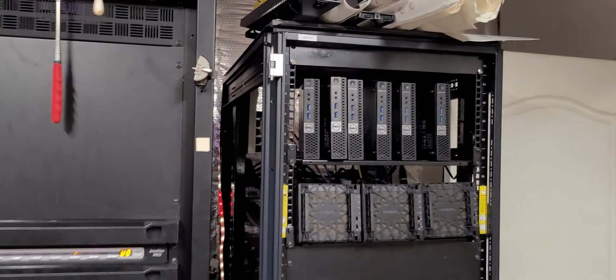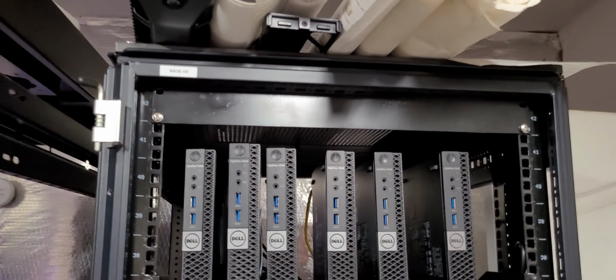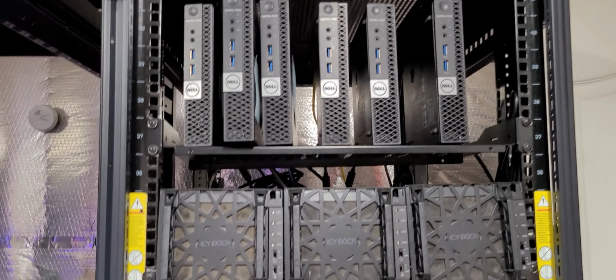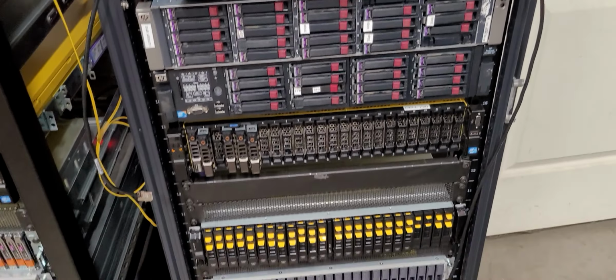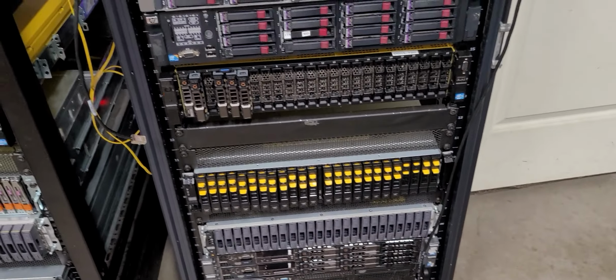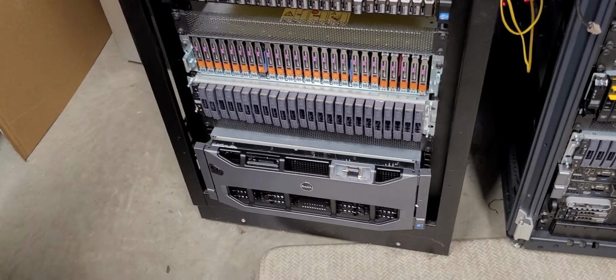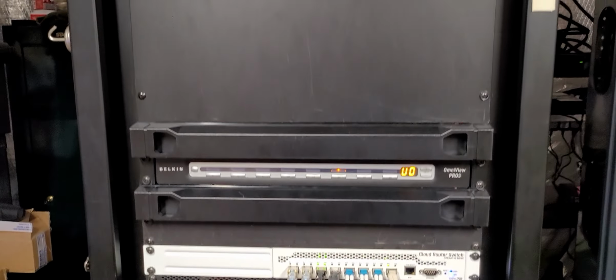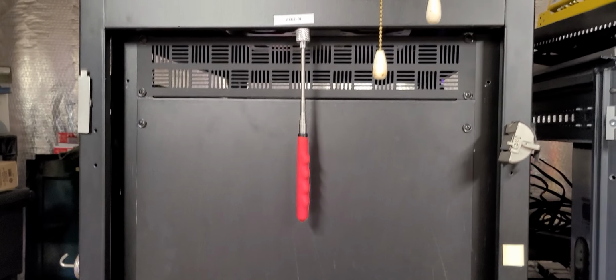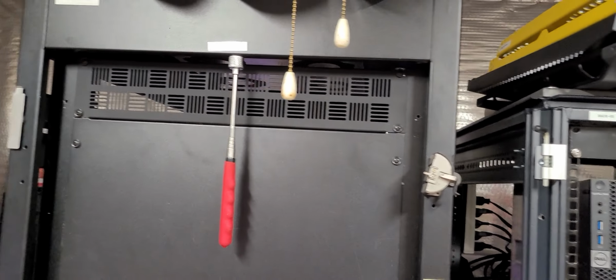Now, obviously, the square footage, that's height, width and length of the room, the metals that are in the room, and most importantly, this really does matter, your rack or your enclosure structure. Now, I'll tell you once again, and I've said this 100 times, I'll say it again. Never, ever put your IT gear inside wood enclosures for any reason. Wood is bad when it comes to electronics. I even did a video where some wood got burned from the electronics because they're not conducive to each other.